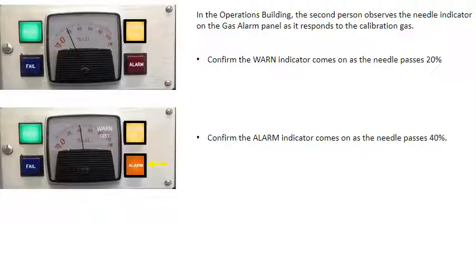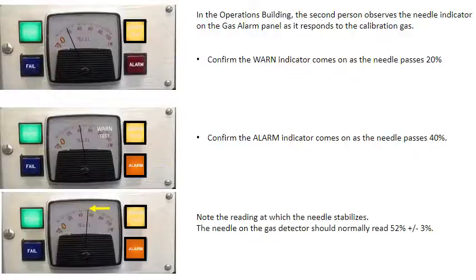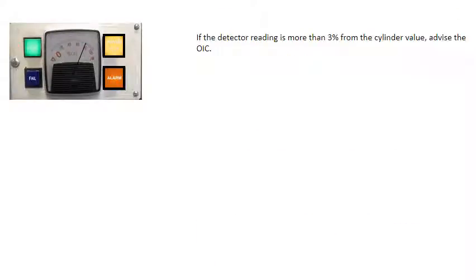Confirm the alarm indicator comes on as the needle passes 40%. Note the reading at which the needle stabilizes. The needle on the gas detector should normally read 52% plus or minus 3%. If the detector reading is more than 3% from the cylinder value, advise the OIC.